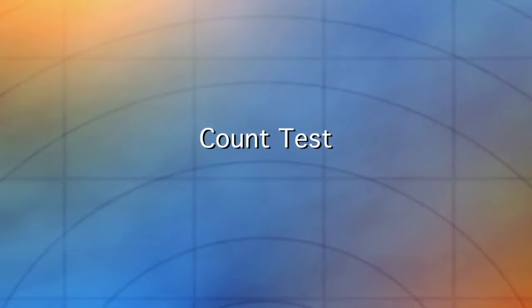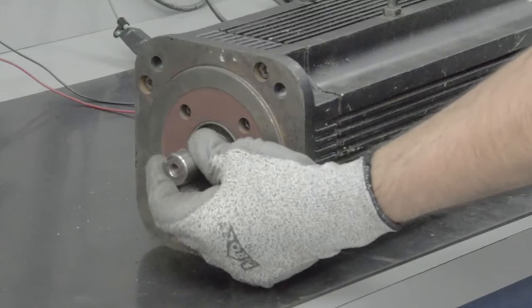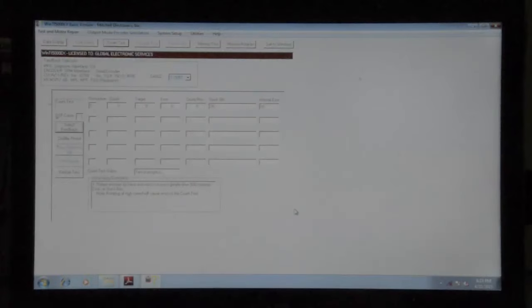Now we can proceed to the count test. To do this, we manually turn the shaft. First count, good. Second count, error. Third count, good. Fourth count, good. As you can see, the encoder has failed the count test in the second revolution.